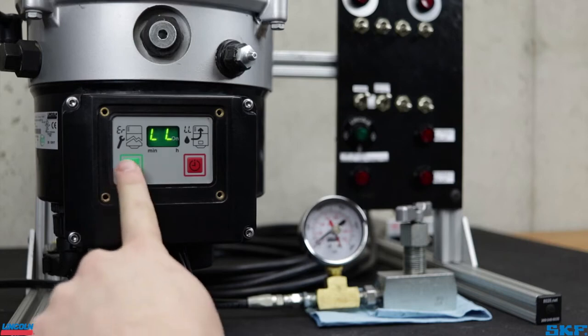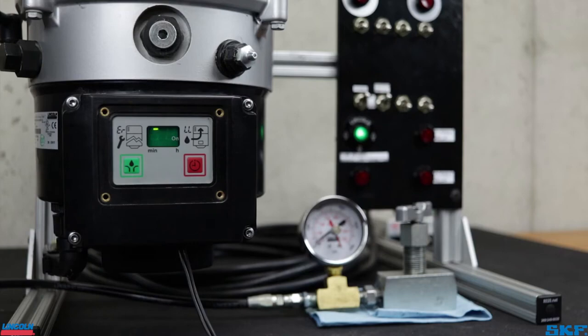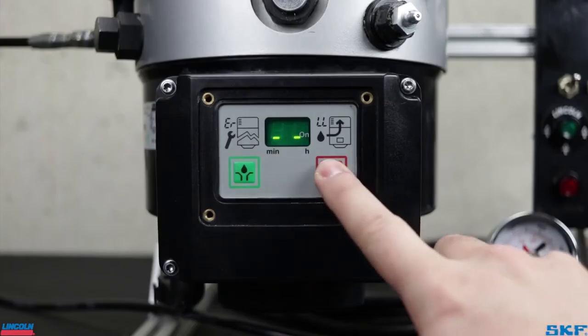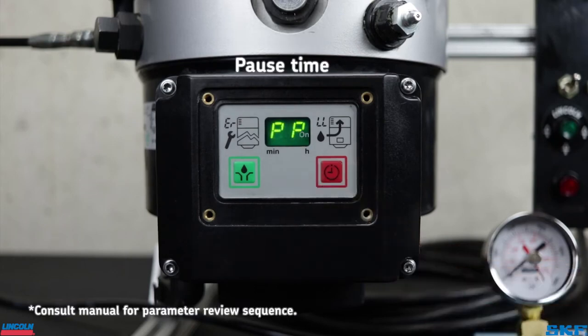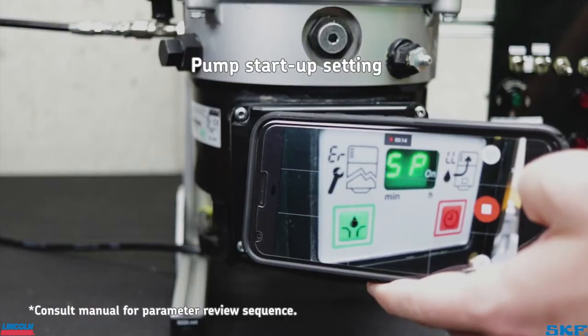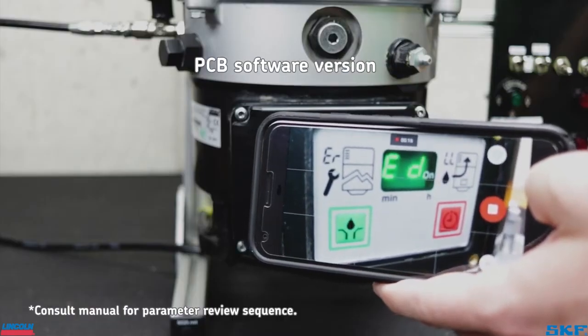Error codes can only be cleared by initiating another loop cycle, which must run through entirely without any issues. Additional to fault acknowledgement, this button also allows you to review the current parameters saved to the pump. Press and hold this button for 2 to 3 seconds, and the screen will flash a series of letters and numbers. This happens pretty quickly, so I would suggest pulling out your smartphone or a camera to record the screens, then play back slower to write everything down.